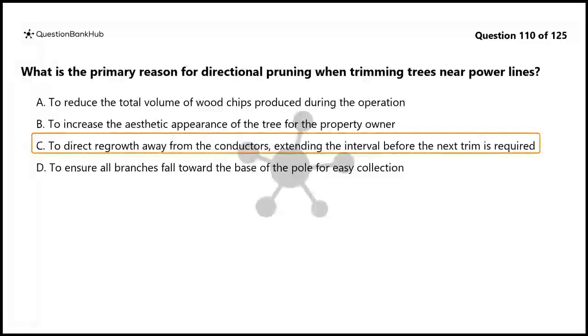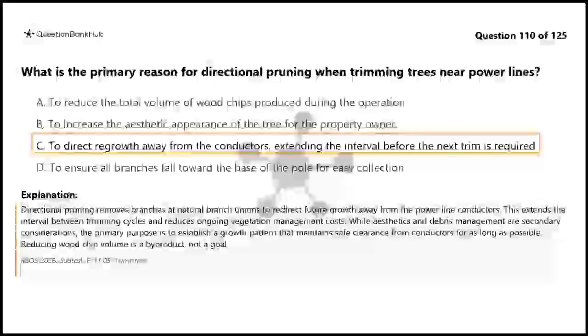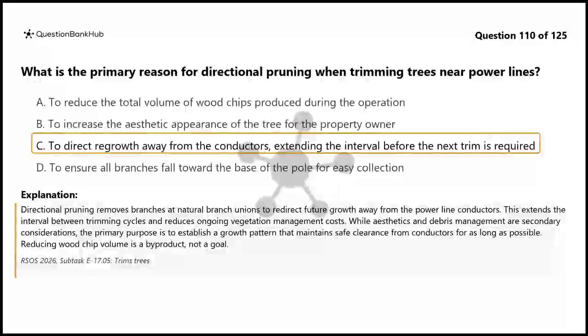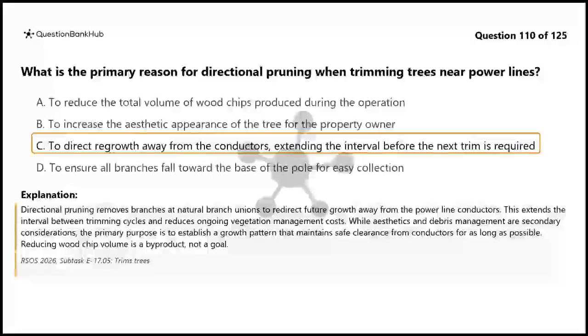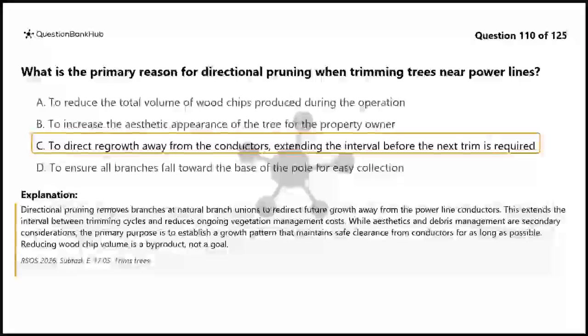The correct answer is C. Directional pruning removes branches at natural branch unions to redirect future growth away from the power line conductors. This extends the interval between trimming cycles and reduces ongoing vegetation management costs. While aesthetics and debris management are secondary considerations, the primary purpose is to establish a growth pattern that maintains safe clearance from conductors for as long as possible. Reducing wood chip volume is a byproduct, not a goal.